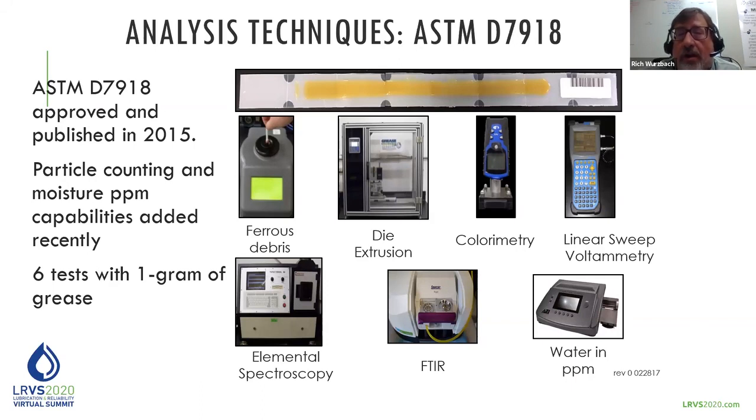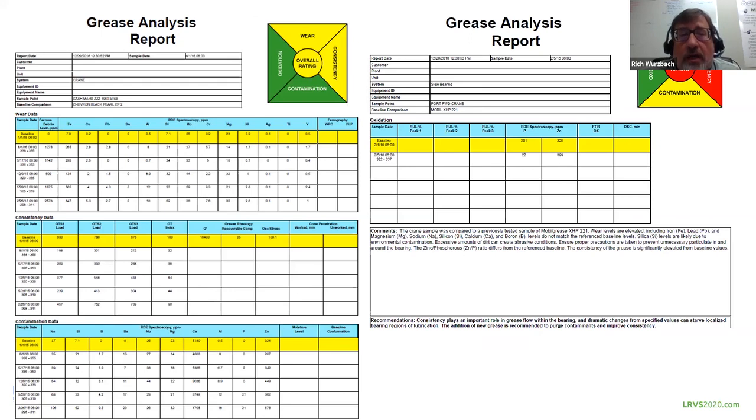That's actually a layer of grease. It happens to be new grease, and it's in various sections that can be peeled away. One of them can go right into a ruler vial to give us a consistent thin film for measuring the presence of the antioxidants. And that really goes to some of the examples that I've added in here. Here's some of the report data that we're getting out of the analysis, but we're really able to do 10 different tests, including looking at some of the metals through metal spectroscopy. We're using RDE there, again using the ruler technology for antioxidant levels, measuring the consistency of the grease.